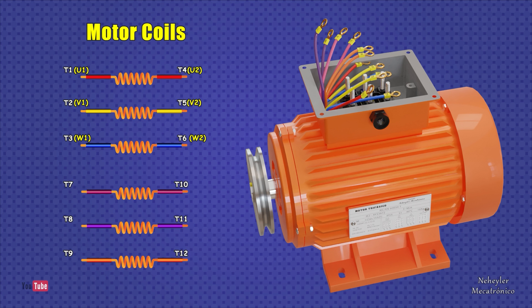The same happens with the terminals of the last three coils. It is designated from terminal 7 to 9 on one side. At the other end of the coils, terminals 10 to 12 are named if based on the NEMA standard, or have letters U, V, and W sub 3 and sub 4 if manufactured under the IEC standard.